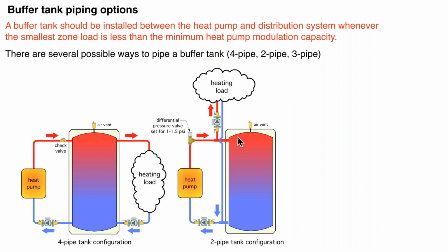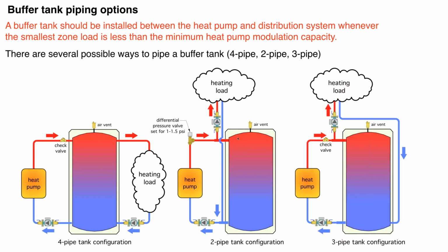So we've talked about over here on the left a 4-pipe configuration, and then I'm showing you a 2-pipe configuration. So what do you get when you average 4 and 2? Well, you get 3. And here's a 3-pipe configuration. And I really like this with a heat pump. What this does is it gives you direct to load on the supply side. So we still have that ability to take heat directly from the heat pump and take it right out to the load without first going through the buffer tank.